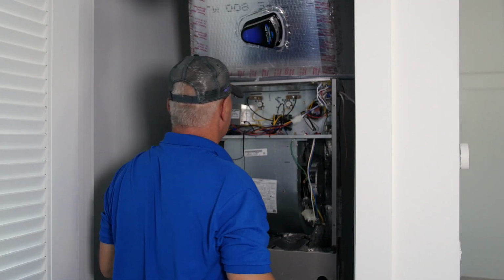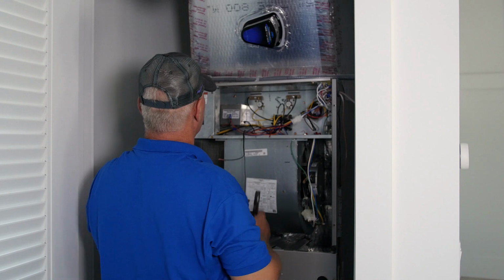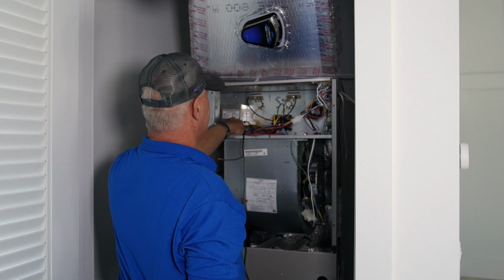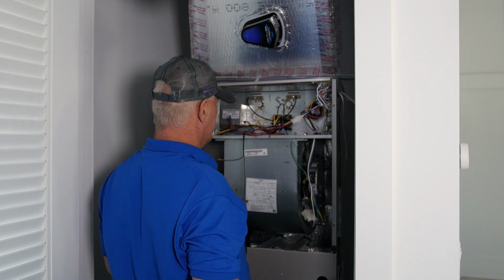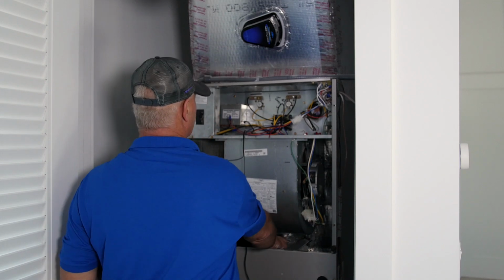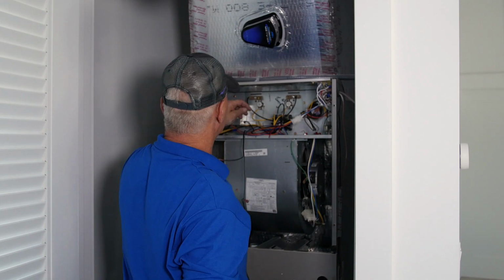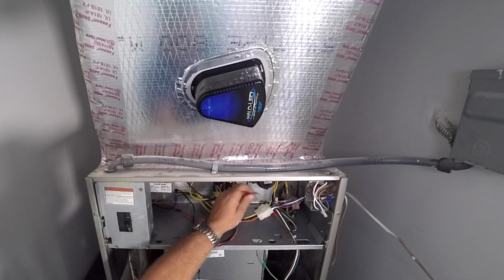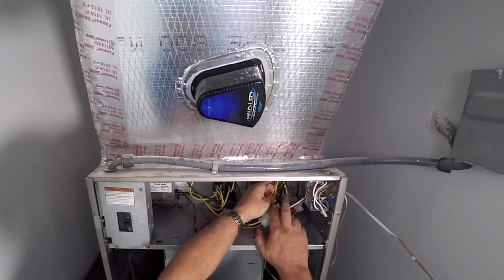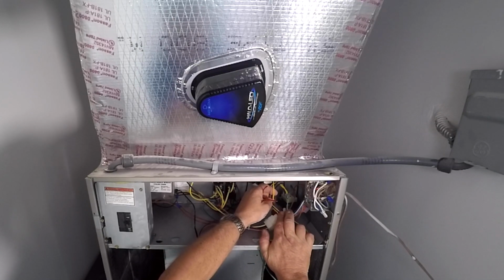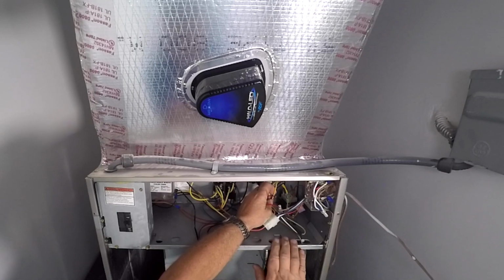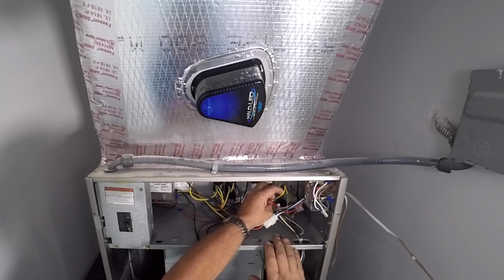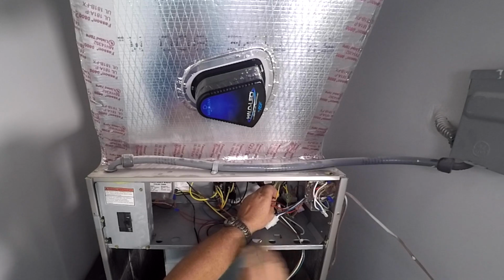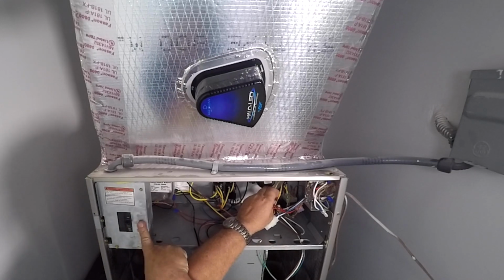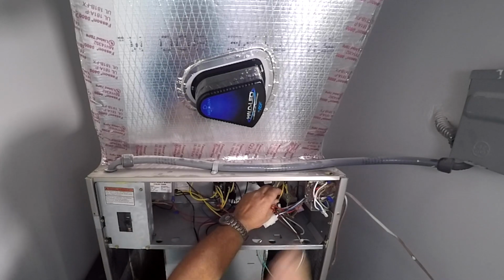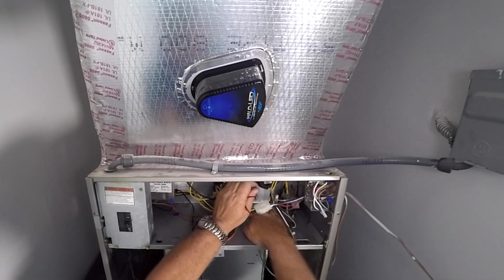Using the air switch kit is very simple. I have already set my transformer in here. It is set up for 240 volts, as that is the voltage of this particular unit. For power, I am going to connect off of the incoming feed of the transformer in the unit, the existing 240 volt feed. Be totally aware to shut your power off to the unit before you ever open the cover and reach in here.